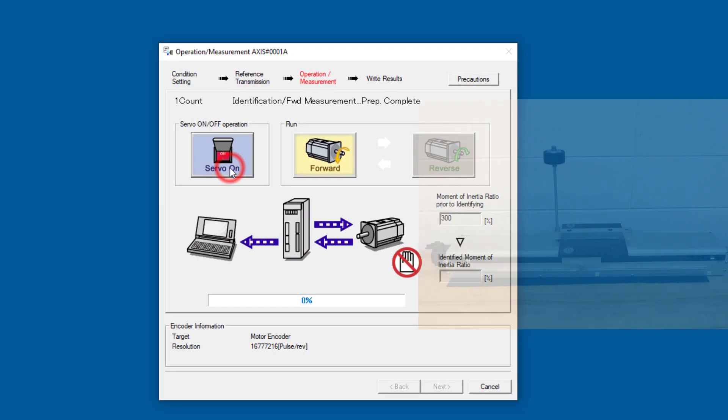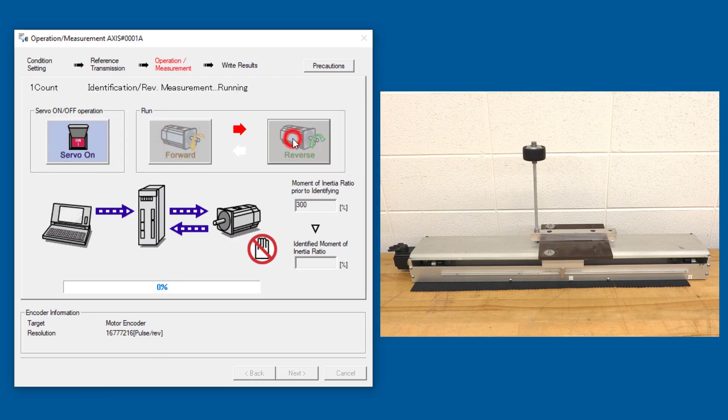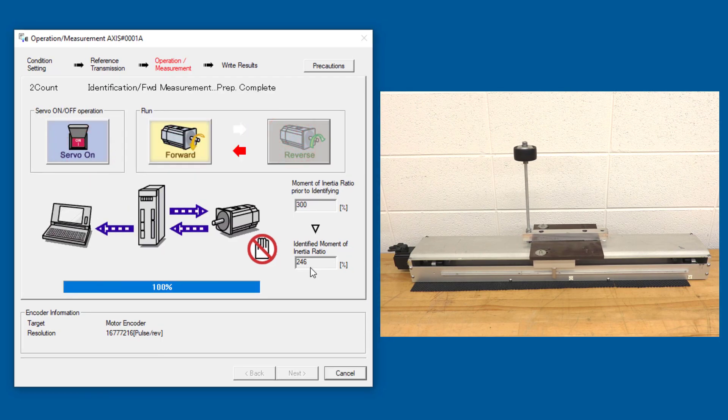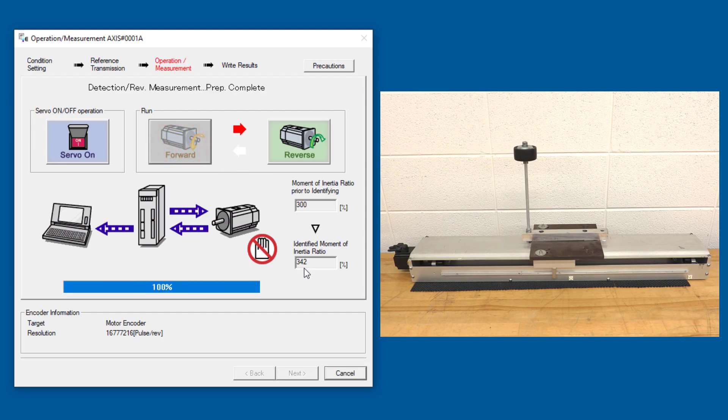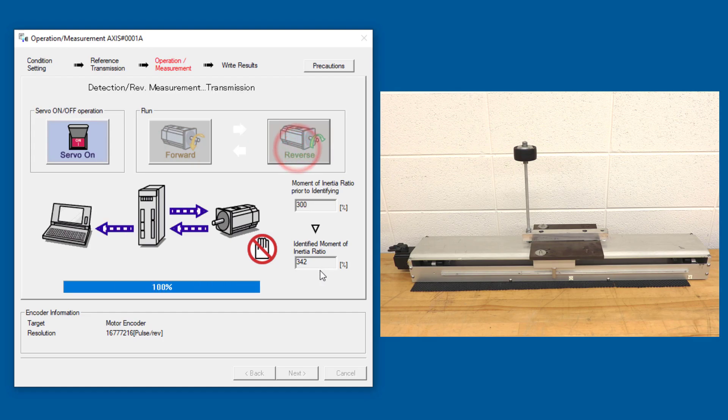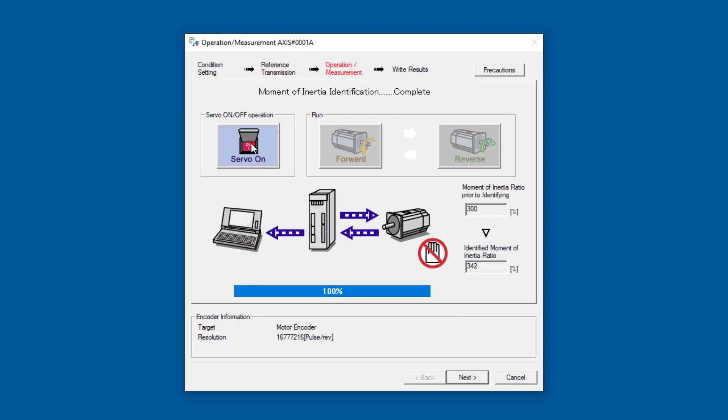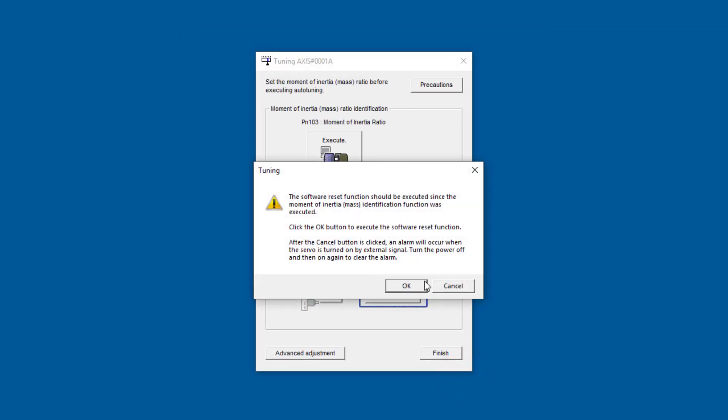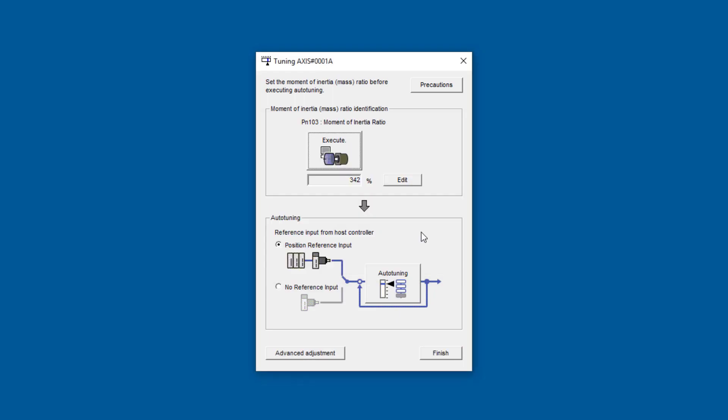Now I'll servo off and let's go back in here to execute the inertia ratio. If this speed is acceptable, we'll just leave it at default and go to the next step. Start and next. Servo on. We'll do a forward move. And a reverse. It's iterating to find the moment of inertia ratio here. And it looks like it's settled on 342%. Alright, I'll turn off the servo. And continue here to write the result into the parameter and finish this step. Software reset is prompted here. We'll do that.